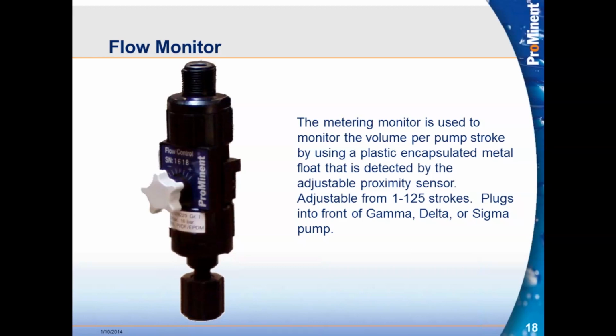Remember, 125, that might sound like a lot of strokes, but if we're talking about a gamma L pump, 180 strokes per minute maximum, if we're running at that maximum speed, that's less than 1 minute of runtime. So we're not missing that much flow necessarily into the system before we're notified about it. So sometimes, especially if it's a chemical that off gases, we want to give it a chance to off gas before we consider that the pump going into fault.